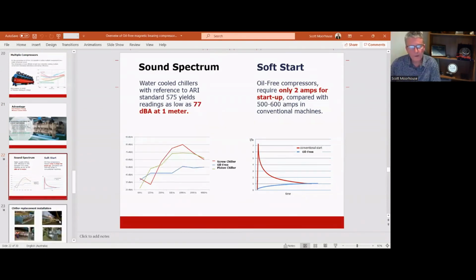Also, the fact that we don't have any mechanical touching of bearings means we don't have any vibration. If we don't have any vibration, then we can have a very low sound. So the pumps are louder than the compressors in the plant rooms when you're using magnetic bearings. And we can have as low as 77 dB at 1 meter for a magnetic bearing compressor. Also, because we're just levitating the shaft and spinning the compressor up to speed, we only need 2 amps to get the compressor going and start spinning off. Compare that with a conventional screw machine at the same capacity, where we'd be using about 500 or 600 amps to get a conventional screw up and started. So we don't have any high inrush current affecting the motor windings.